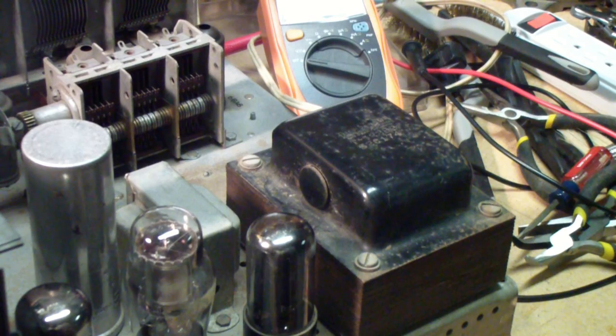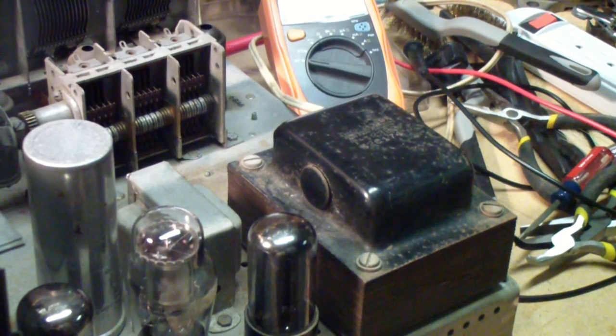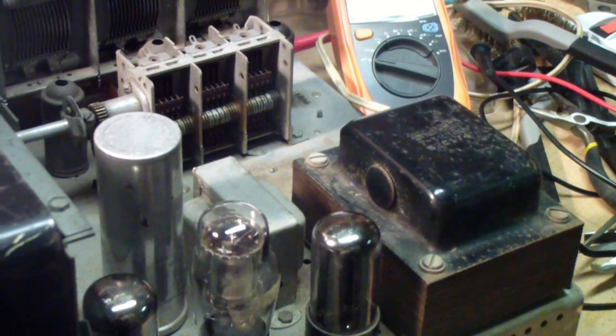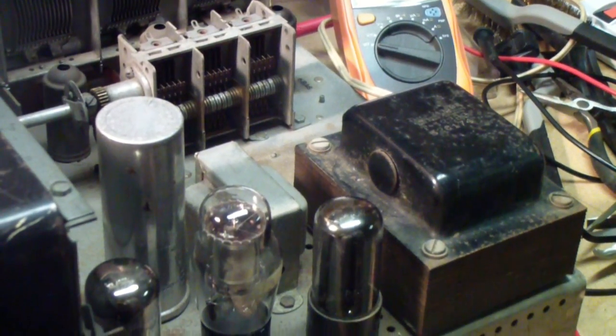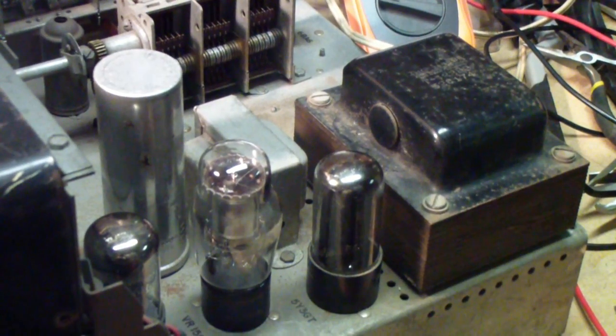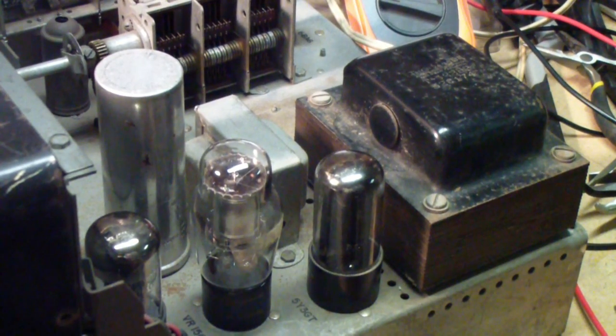What I mean by that is, you need to actually test to see if you have any line voltage leaking to the chassis or any metal parts where you could make contact with it. If you don't know what I mean by that, it's best to just avoid this altogether, or at least use an isolation transformer in addition.